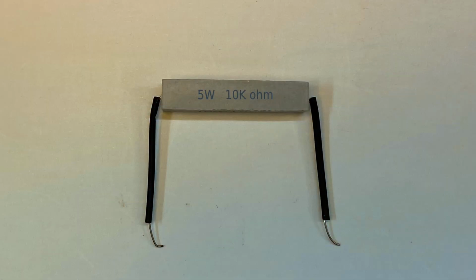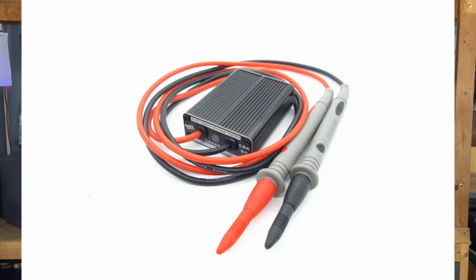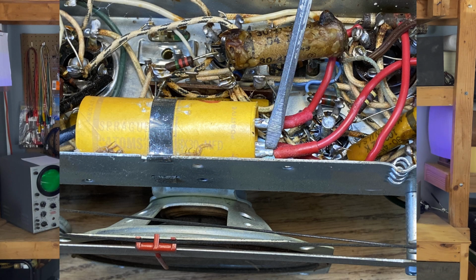Before you touch anything under the chassis, make sure the capacitors are safely discharged. The safest method is to use a bleeder resistor or a purpose-built capacitor discharge tool. While it may be tempting to short the capacitor terminals with a screwdriver, that's not recommended, as doing so can damage the capacitor or other nearby components.